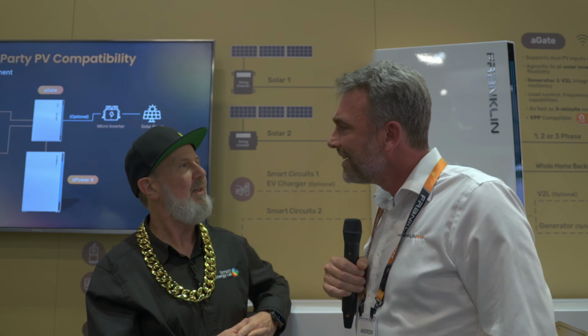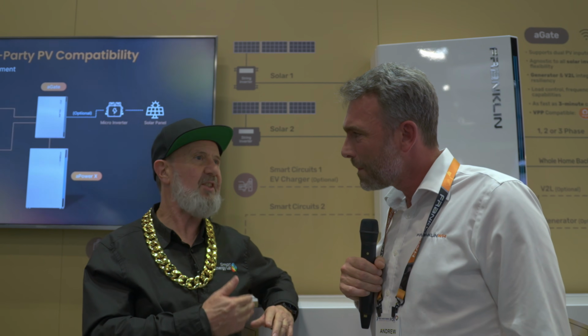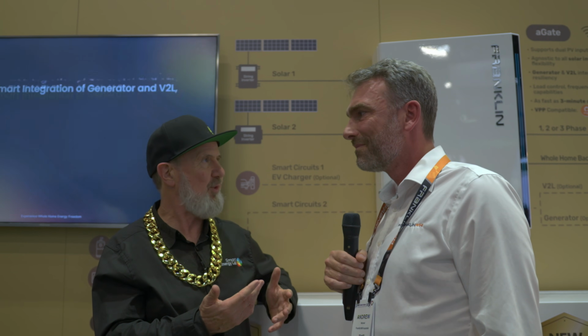Off-grid, of course you've got the generator control function, which is essential. Yeah, that's really good to hear. You can do quite a high level of oversizing on the PV side because we've got both frequency shift and the relay. You can whack 20 kilowatts of PV AC coupled into the gateway, and then 2 or 3 batteries would serve most homes for off-grid. So the relay can disconnect the solar if there's any issue with too much reverse power.